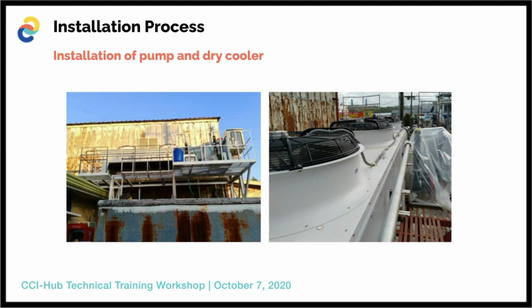The dry cooler is designed to operate at 0 to 80 hertz for the summer seasons, and it is fully engineered based on the design, using a variable frequency drive or VFDs. Due to the results of our 4 previous Waterloop projects, we decided to focus on control over the dry cooler operations. The main reason is that Subic Bay is near the ocean range with high humidity. Also, this will achieve the manufacturer's required water entering temperature, which is about 25 to 28 degrees Celsius on the liquid-cooled condensers.